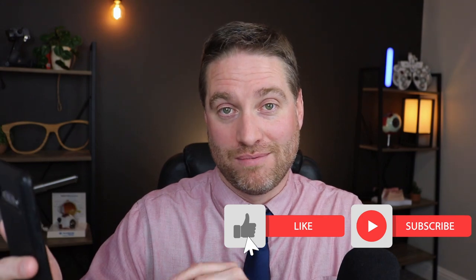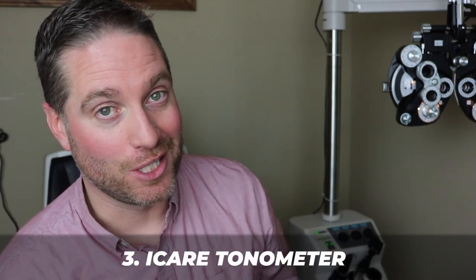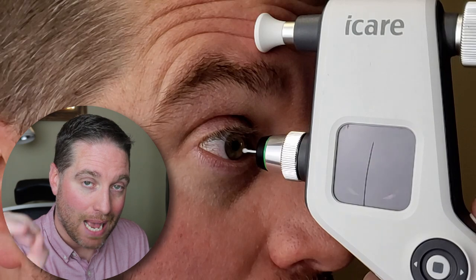Just really quickly — for the statistics of this video, I measured my eye pressure 82 times for you. Next up on the list, and my personal favorite, is the iCare tonometer. This has a small magnetized probe, and when activated it will come out and tap the cornea and rebound back — that's actually how it measures eye pressure. It measures how fast or how hard the rebound is, so this is considered a rebound tonometer.